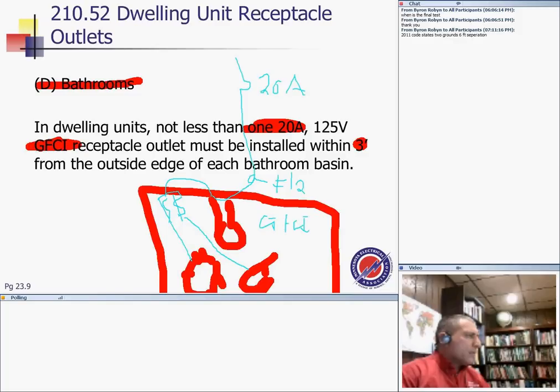How many of you say you can't do that, and how many say you can? I say you can. See, a 20 amp circuit feeds the receptacle, and that's okay. And I can also feed the fan and the light from it. The installation, guys, is okay, correct, no problem. Can I bring another circuit for the fan and the light? No problem. You can if you want to.